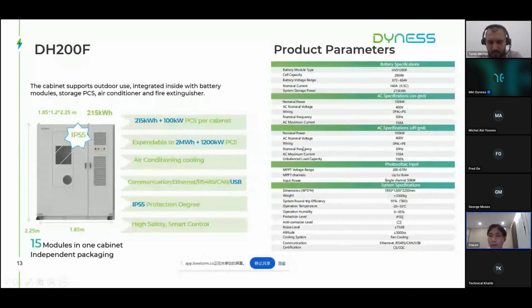So we can go briefly into the specifications. For the battery cell, it's 280 ampere hour, and the battery voltage is from 600 to 800 volts. The nominal current is 140 ampere, so that is 0.5 C. We are using this in many C&I solutions at actual project sites. You can put a maximum of 15 modules in one cabinet.